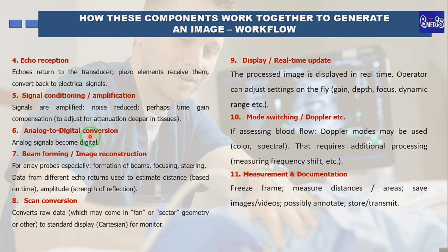Then we have the analog to digital conversion. Analog signal becomes digital. Beam forming and image reconstruction. Scan conversion, where they convert raw data which may come in fan or sector geometry in order to standard display for the monitor. Then we have the display or the real-time update. The processed image is displayed in real time. Operator can adjust settings on the fly, that is gain, depth, focus, dynamic range.